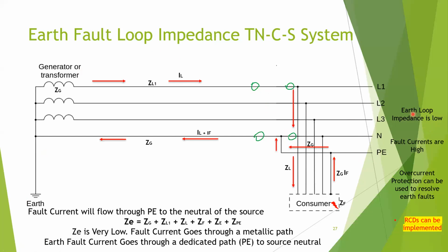And here also, in all TN systems, earth loop impedance is low. So fault currents are high, so less sensitive devices can detect faults. Protection coordination is easy. With the earth loop impedance, you can easily determine the path, a full metallic path. Those are the characteristics of a TNCS system. So RCDs can be implemented.